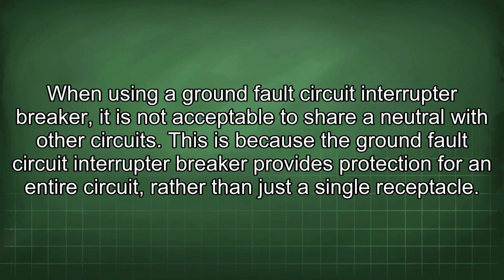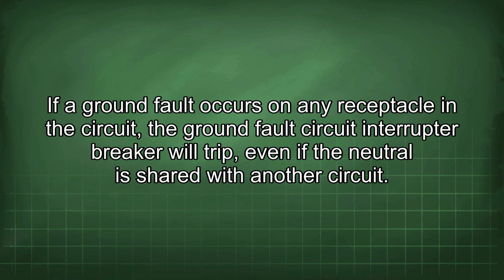When using a ground fault circuit interrupter breaker, it is not acceptable to share a neutral with other circuits. This is because the ground fault circuit interrupter breaker provides protection for an entire circuit, rather than just a single receptacle. If a ground fault occurs on any receptacle in the circuit, the ground fault circuit interrupter breaker will trip, even if the neutral is shared with another circuit.